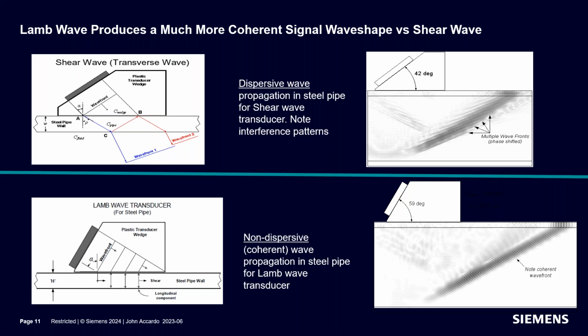And if we look at what that does to the receive signal, and before I say that, what the real benefit of a Lamb wave transducer is, and why it's so profoundly superior to shear wave, is that when you use Lamb wave technology, the pipe is actually part of the transmission mechanism. So you're actually exciting the pipe wall. You're just giving the pipe energy and letting the pipe do the work.